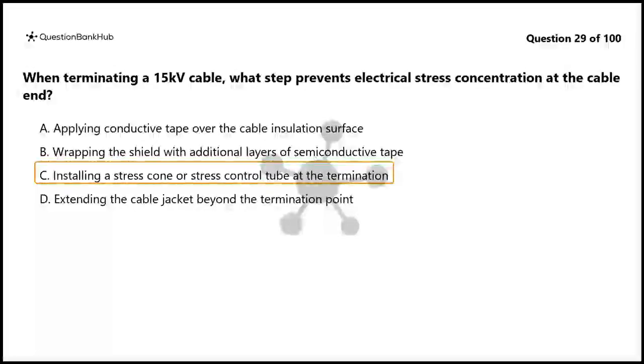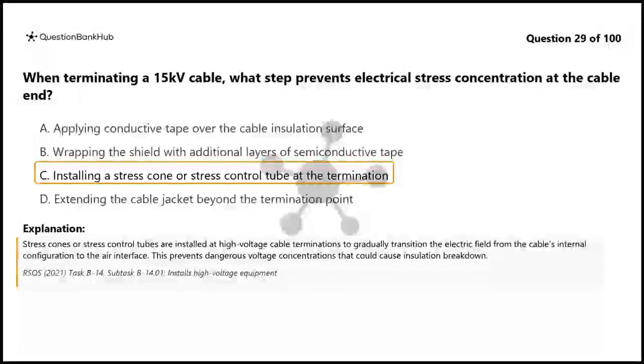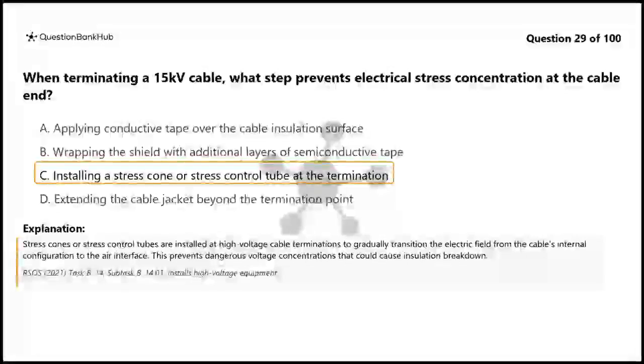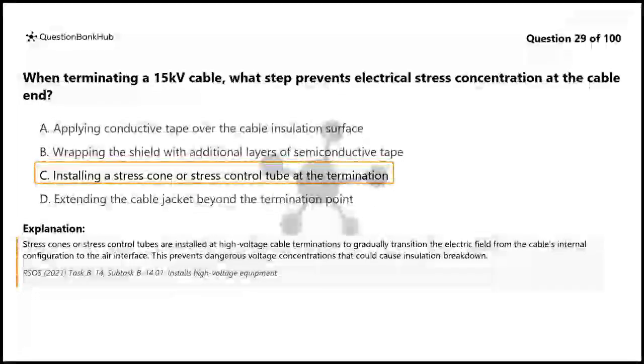The correct answer is C. Installing a stress cone or stress control tube at the termination. Stress cones or stress control tubes are installed at high-voltage cable terminations to gradually transition the electric field from the cable's internal configuration to the air interface. This prevents dangerous voltage concentrations that could cause insulation breakdown.